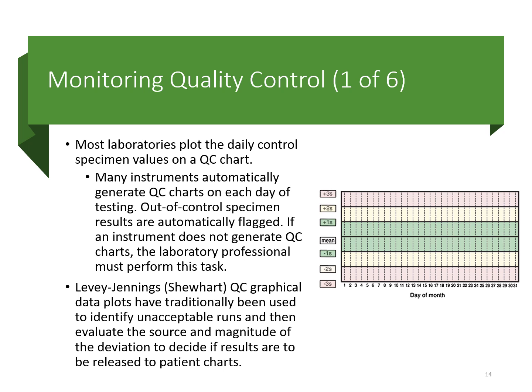So what we use is a Levey-Jennings chart, and it's something similar to what you see here. What that does is give you a visual for plotting that data, and then it helps you visualize when something is out. So you see here where we discuss determining that mean, which is your average. And then beyond that, you have your standard deviations, so you have your plus side and your minus side. When we talk about these standard deviations, we're going to get a little bit more detail of what these actually mean as we go forward.